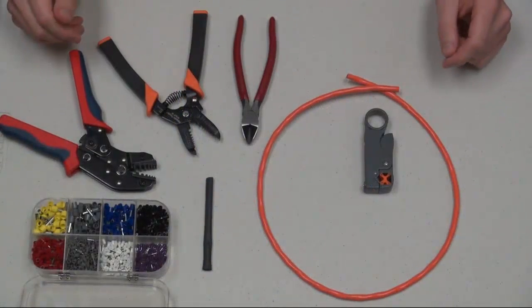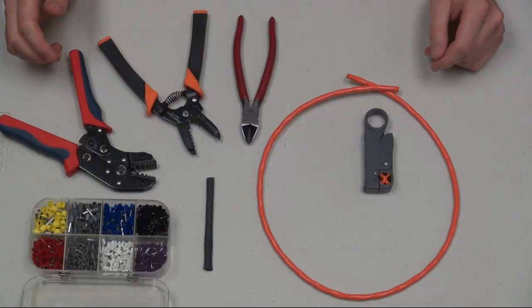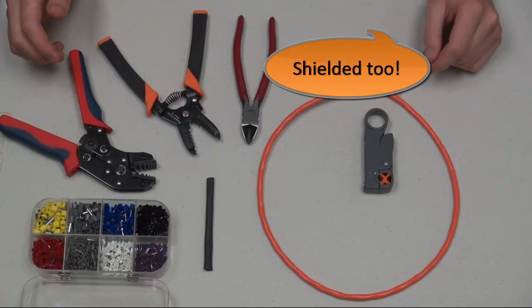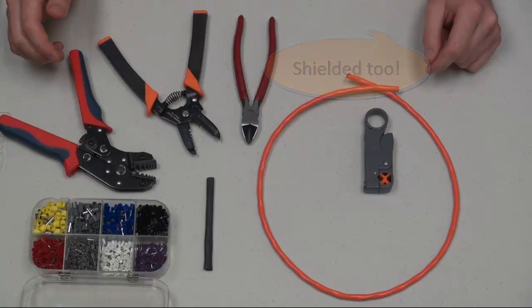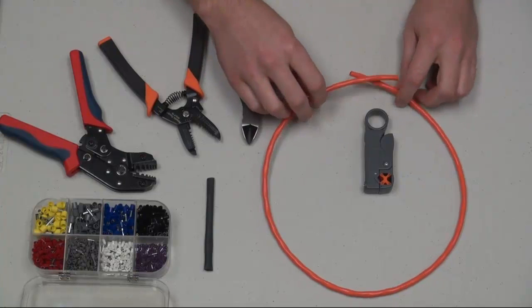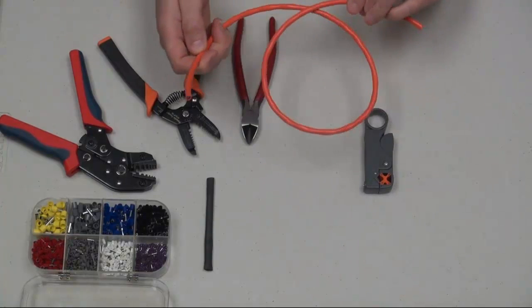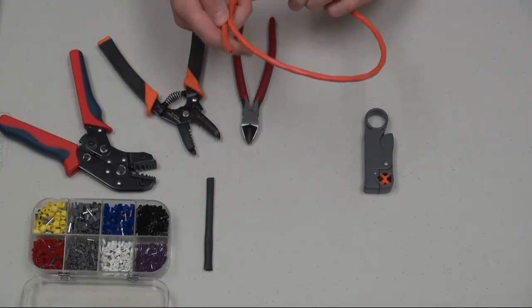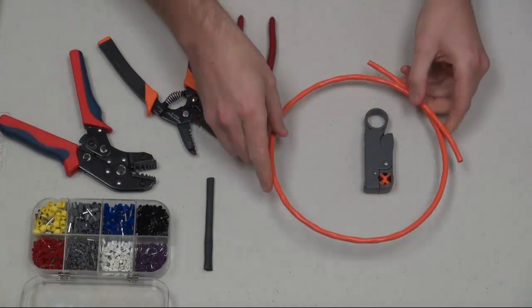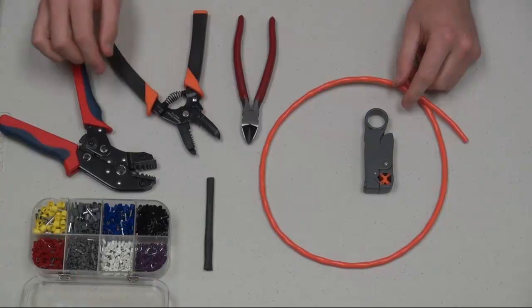All is very much acceptable, and there's not exactly a written standard for which those should be. The only real requirement here is that it should be twisted, stranded pair, and we do recommend a minimum of 18-gauge wire should be used. It's also important to note that you'll want to make sure that you do not ever exceed the minimum bend radius of each particular H1 cable, and that is manufacturer-recommended, so you'll have to speak to whoever your cable manufacturer is directly to discover that.